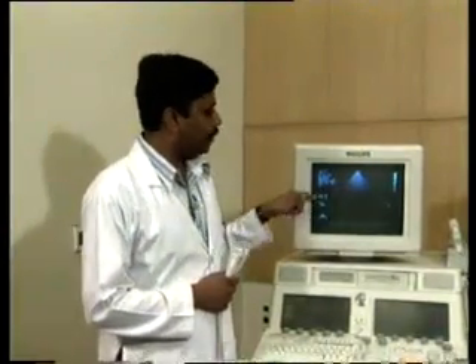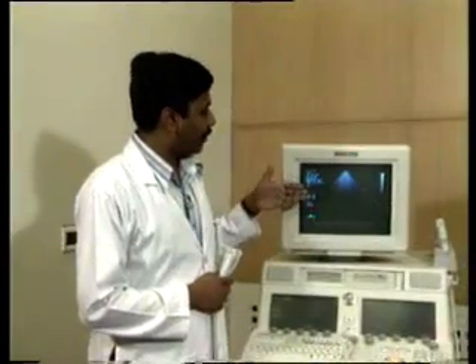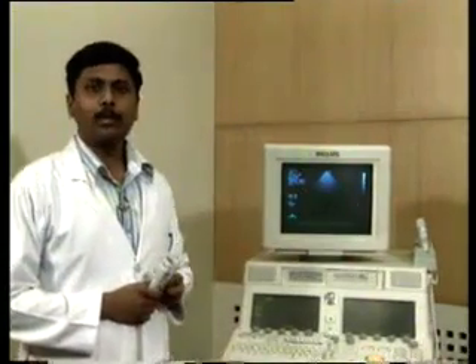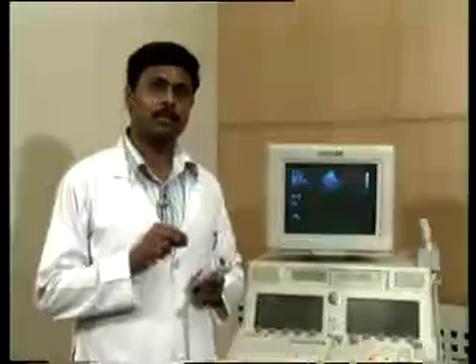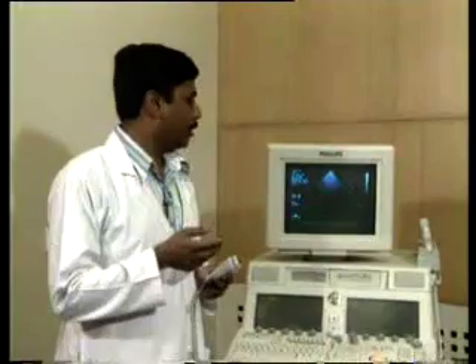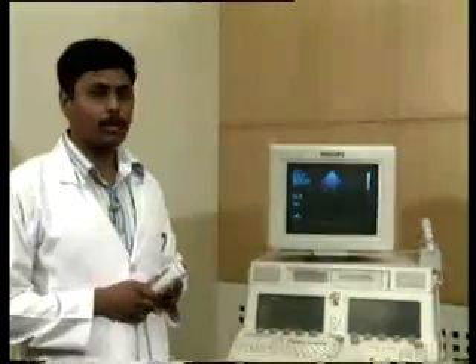Like in this, if we want to image a cross section of the heart, we'll have to move the ultrasound beam from one end to the other end. The earlier probes had mechanical motors fitted within the probes that used to rotate the piezoelectric crystal to move the beam. Now these probes were very bulky and outdated, and are not used nowadays. The technology that we use nowadays for moving the ultrasound beam is predominantly electronic.